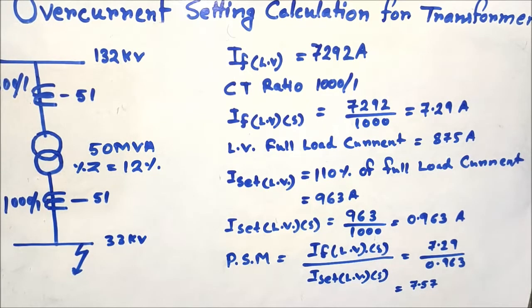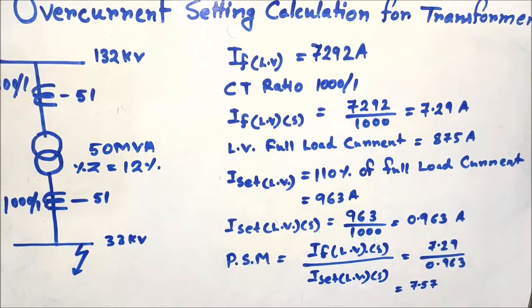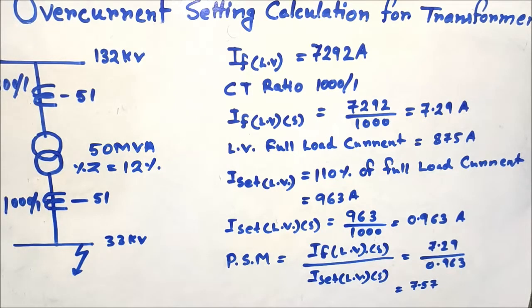The fault current close to the 33kV bus on the LV side is 7292 amperes, or 7.29 kilo-amperes. The CT ratio on the LV side of the transformer is 1000/1. This fault current reflected to the secondary side of the CT is 7292 divided by 1000, which equals 7.29 amperes. This fault current will be sensed by the overcurrent relay connected on the secondary side of the LV CT.